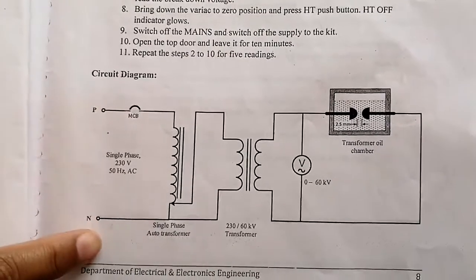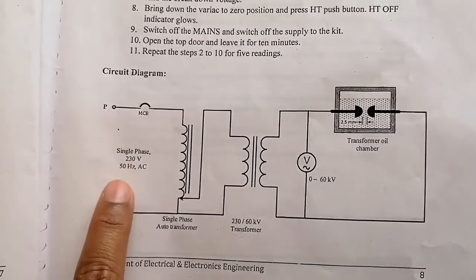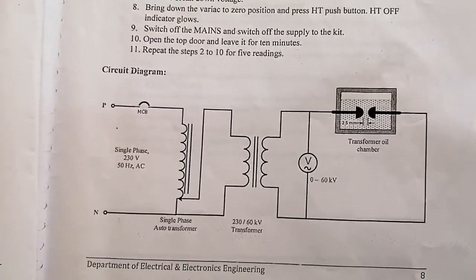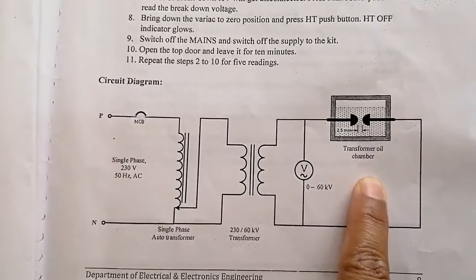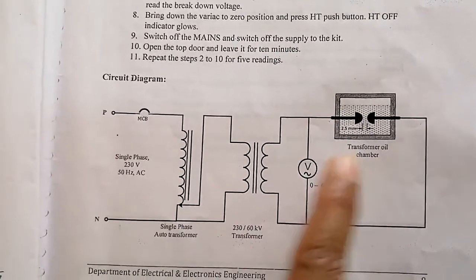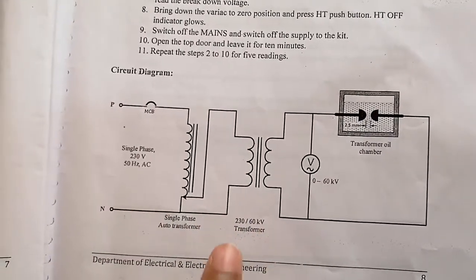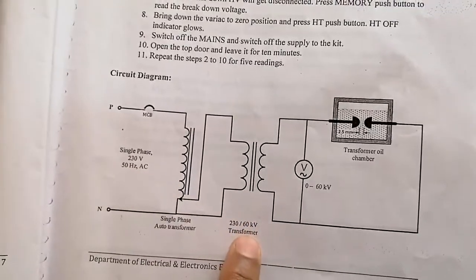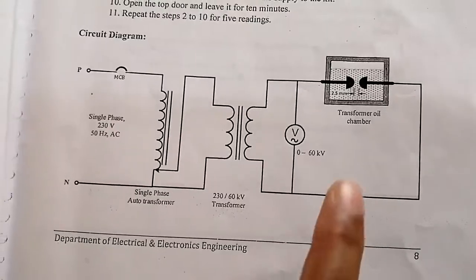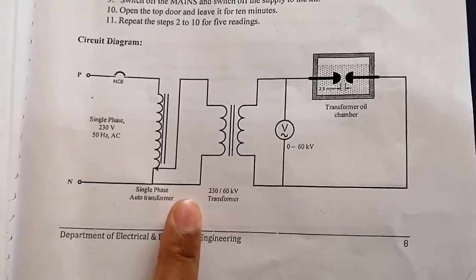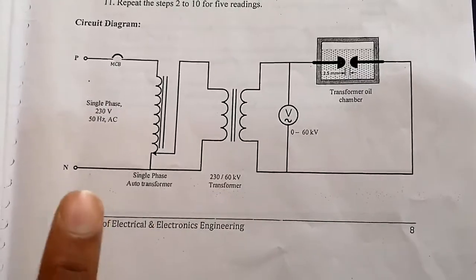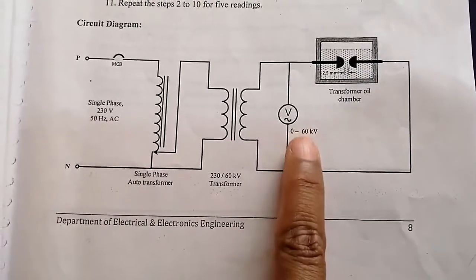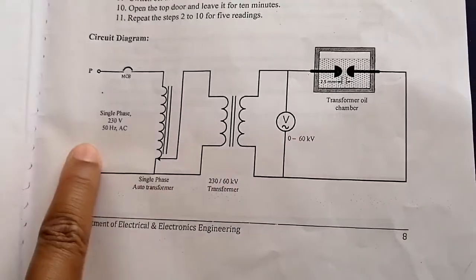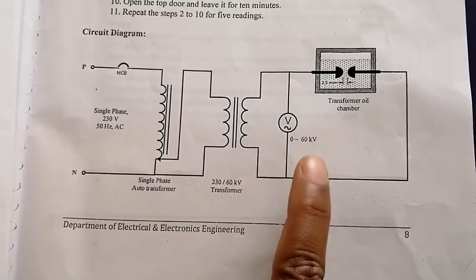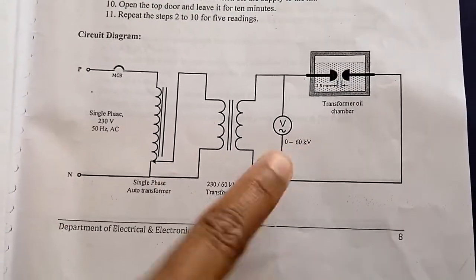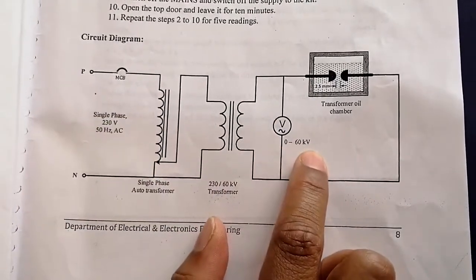You can observe the source we receive from outside is 230 volts single phase 50 Hz AC. I have to test the transformer oil in the kilovolt range, so I need a transformer which can step up the input 230 volts to a higher voltage of, for example, 60 kilovolt. So we need a 230 V to 60 kV transformer, and also an auto transformer, and an AC voltmeter, because the applied voltage is AC. The voltmeter range is 0 to 60 kilovolt.